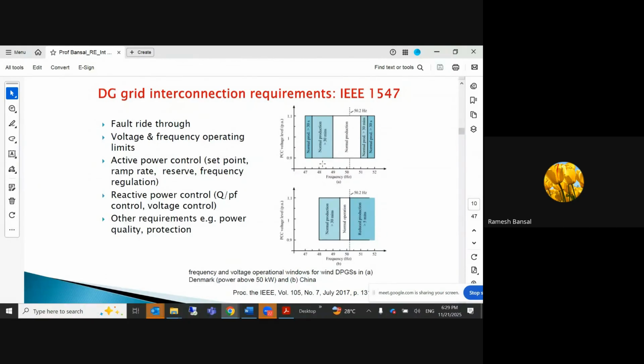Fault ride through capability refers to how these renewable power plants behave when a fault occurs on them. The past approach was that when a fault occurs, these renewable power plants would be shut down. But now the technology has improved significantly. They are not immediately shut down, but stay connected, and not only stay connected, but help in recovering the fault conditions.